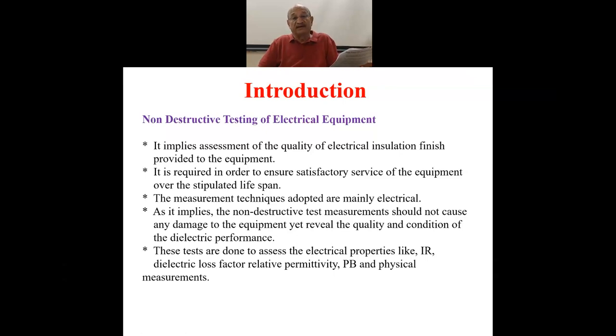The insulation systems in different equipment, you have to visualize a transformer, very complicated, complex insulation system is needed to be provided to the transformers. The transformers will have taped insulation over the windings, that is, you can say, the solid insulation given out of paper, a very special kind of paper tape insulation. Nowadays other materials, that is, plastic, fiberglass reinforced plastic tape materials, etc., are also being given, perspex, etc.